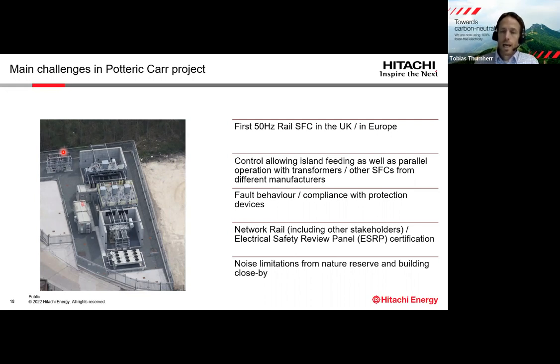The control, as I mentioned previously, has to allow island feeding. So it has to operate as the only source feeding the railway grid, and it also has to be able to operate in parallel with transformers or with other static frequency converters from different manufacturers.